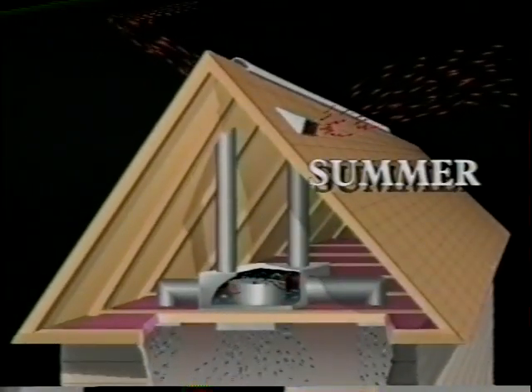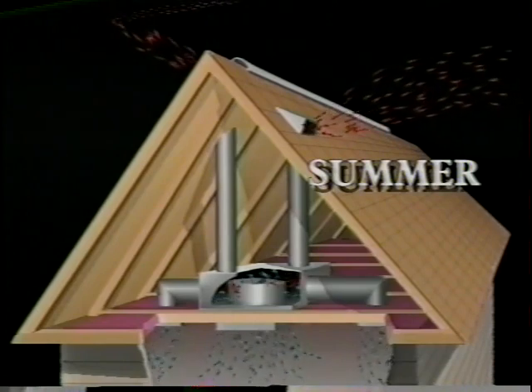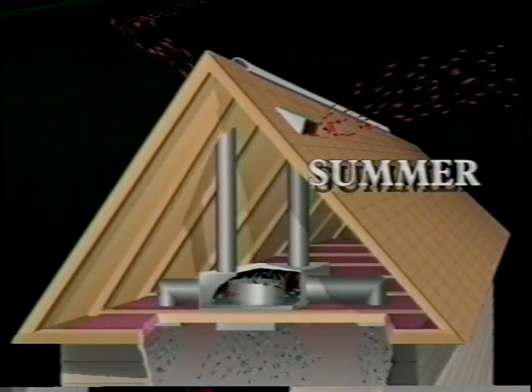In winter, the heat wheel absorbs heat from air being exhausted, then gives it to fresh incoming air. This process allows cold air to be warmed before entering the living space. During the summer, the process is reversed. The heat wheel picks up heat and moisture from incoming air and gives it to outgoing stale air. The fresh air is cooled and dehumidified, providing comfort and eliminating the problems associated with a home being tightly built. It's like living in a climate where a gentle breeze is always blowing. The temperature never gets above 78 degrees and the air is dry. Meanwhile, the heat recovery ventilation is saving 80% of the air conditioning or heating energy needed for ventilation.